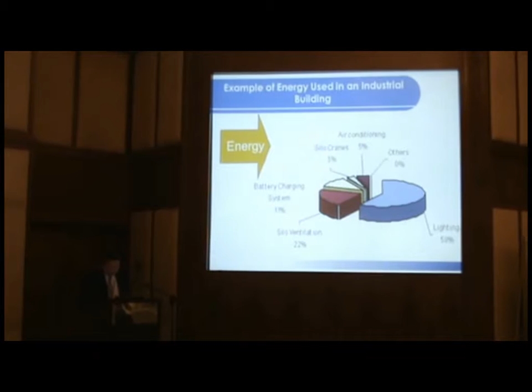But I want to bring your attention that in a building there are two loads that normally occur: variable load, during working time/daytime, and base load, which runs 24 hours. Most of the time we design according to the variable load, but sometimes we don't really look into the base load running 24 hours. I'll share with you the items running 24 hours, what is the culprit there.